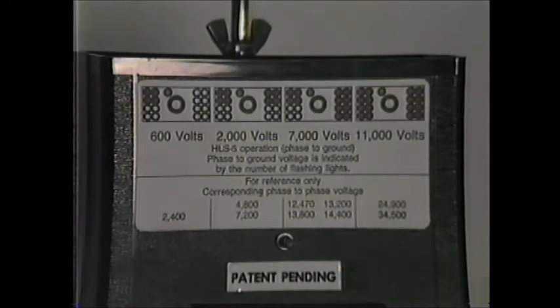Due to the proximity of grounds on underground equipment, the HLS 5 will usually have one more bank of lights lit than would be expected when used in an overhead system. Because induced voltages are not as prevalent on underground systems, customers have not found this to be an operational problem.